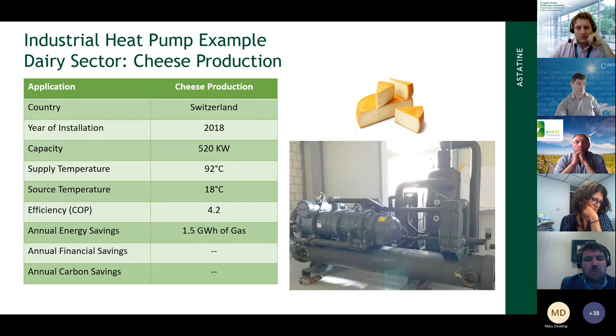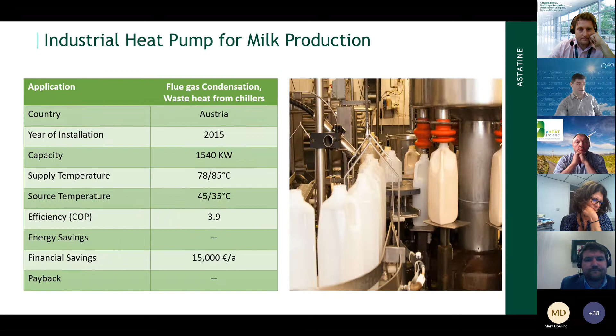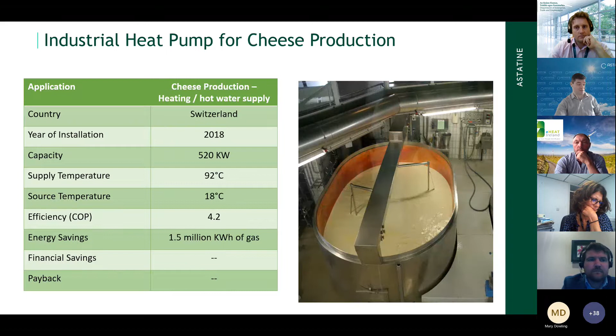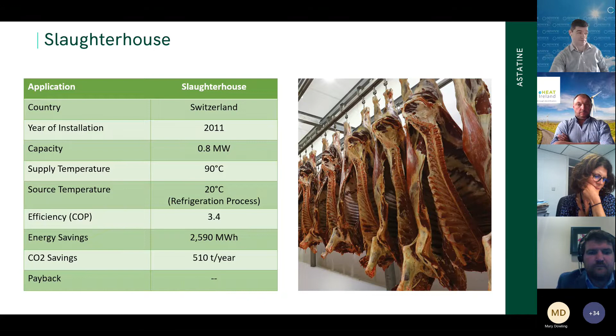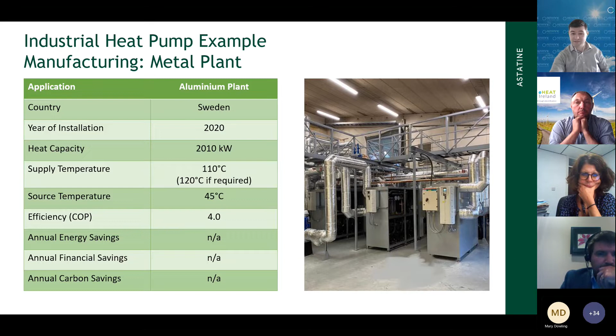I've included a few case studies from Europe of existing dairy facilities: a 90-degree facility in Switzerland at 500 kilowatts, an 85-degree facility at 1.5 megawatts in Austria, and a 90-degree cheese plant in Switzerland from 2018. I like to highlight one in particular - a 90-degree supply that's been running for 11 years in a meat processing facility, showing over a decade of operating experience. A partner of ours also did one in Sweden, notable because the temperature level is higher than most others - up to 120 degrees in an aluminium plant - but there's no reason a food and beverage or dairy facility couldn't utilize that same solution. It's very similar to what we're installing at the distillery towards the start of next year.